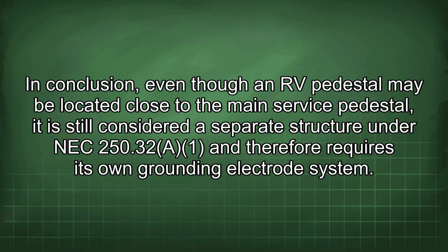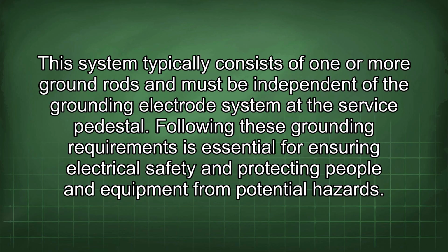In conclusion, even though an RV pedestal may be located close to the main service pedestal, it is still considered a separate structure under NEC 250.32 and therefore requires its own grounding electrode system. This system typically consists of one or more ground rods and must be independent of the grounding electrode system at the service pedestal. Following these grounding requirements is essential for ensuring electrical safety and protecting people and equipment from potential hazards.